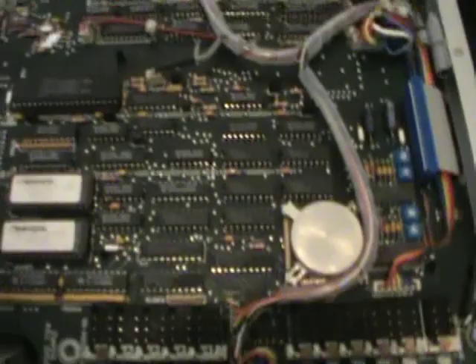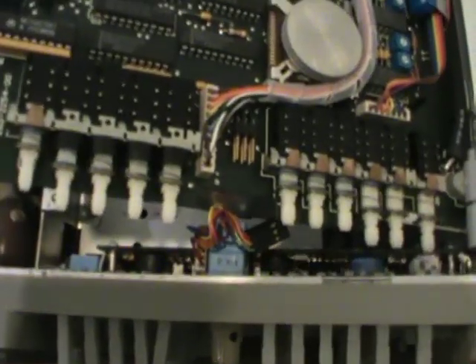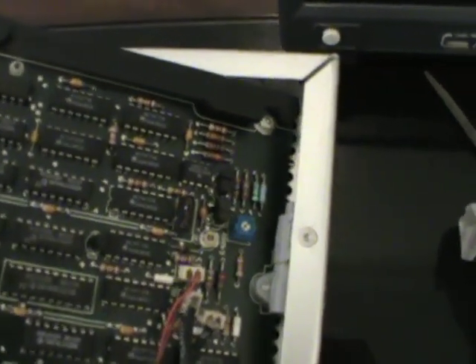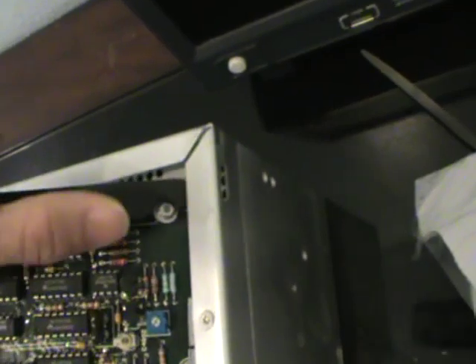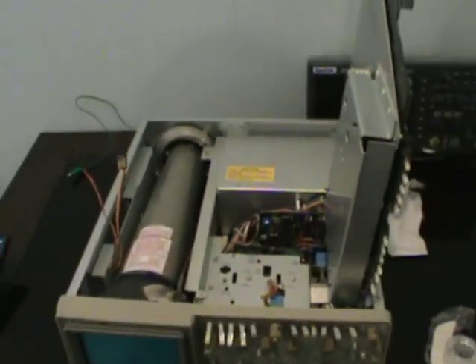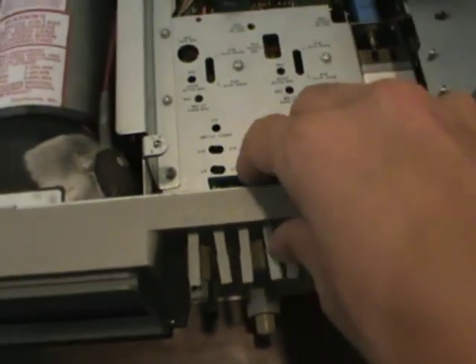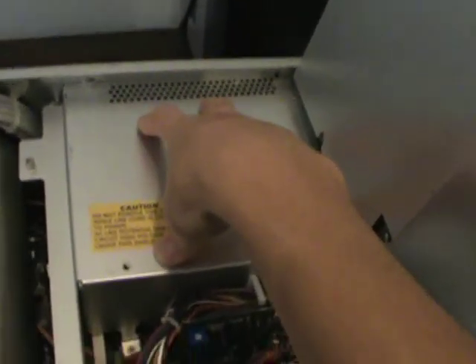You have to remove this connector as well for the cursor. You do that by first lifting the acquisition board. Then disconnecting that. I'll do that right now. Disconnect it. And then here in the back. I'm gonna pay attention here. You want to have this clip here attached. So it's difficult to do with one hand but I'll try. You do this by lifting and then over and then you put it into that hole. It just locks in and then it's now. The scope is now in this service position. You might want to push all these back again as well. Because, you know, these might go into here. And you gotta remove this case as well if you want to get to the power supply. And that's done by screws that are back here mounted at the rear.